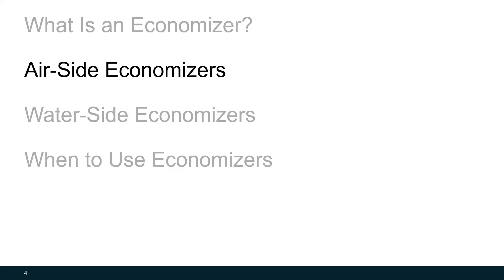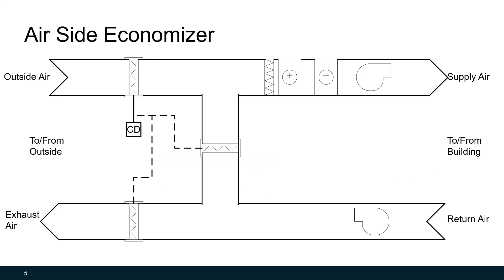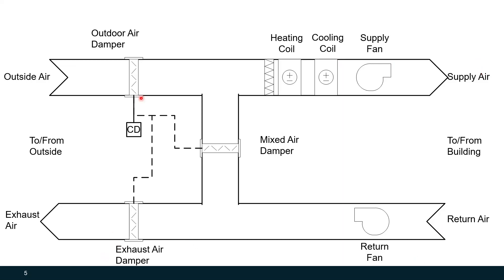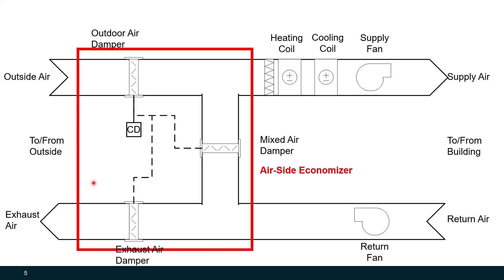So let's start with air side economizers. This is an air handling unit schematic. As you can see, we're bringing in outside air and mixing it with return air, and the air passes through a series of dampers that we use to control the airflow. We then either heat or cool the air as needed, and the supply fan pushes the air into the building. Any return air we don't need is exhausted, which is usually related to the amount of outside air. The three dampers — the outside air damper, the mixed air damper, and the exhaust air damper — make up the air side economizer.